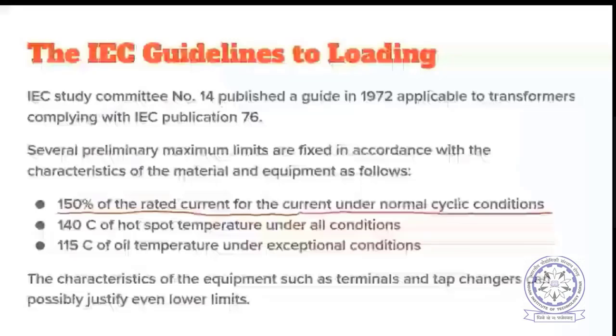And then, 140 degrees centigrade of hot spot temperature under all conditions. In no condition should the transformer temperature be allowed to exceed 140 degrees centigrade, whether in an exceptional load condition or a recurrent load condition. The transformer temperature should never go beyond 140 degrees centigrade, because it will cause drastic aging of the insulation and it may be damaged very soon. The life may decrease very fast.